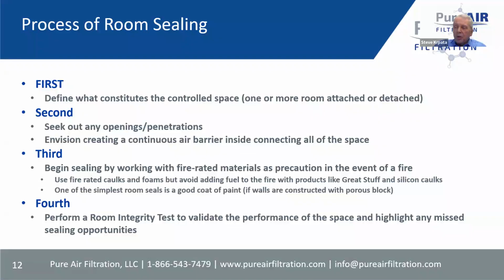We use fire rated materials for those, because if there is a fire, you don't want the material you use adding to it or being fuel for the fire. A lot of times people don't pay attention to that. You see rooms where they've used great stuff or silicone caulks, and all that has petroleum in it, which would add to a fire. So best practice is to use fire rated caulks, foams, and materials to do the sealing.